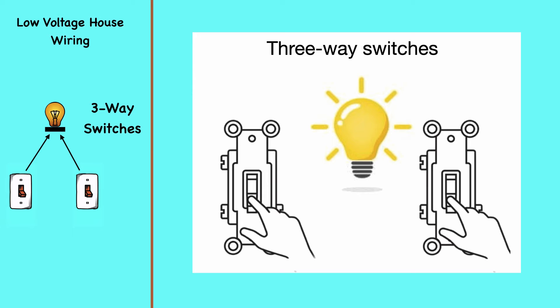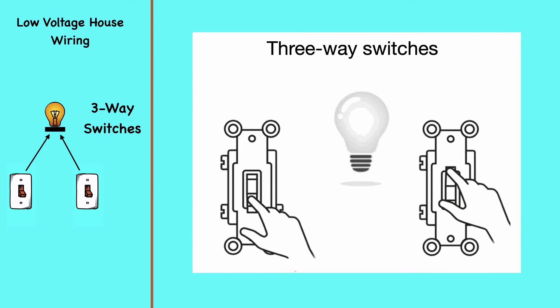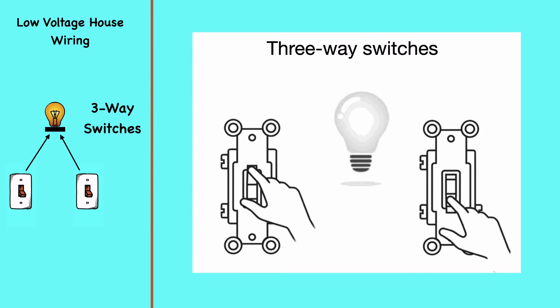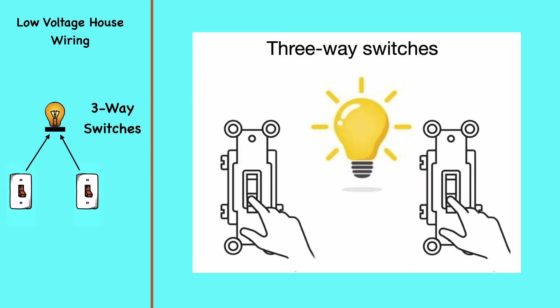The traveler terminals will always be connected from switch to switch. Travelers never connect to a device load or to a source wire. It doesn't matter which traveler terminal is used for which traveler wire — reversing them should make no difference.